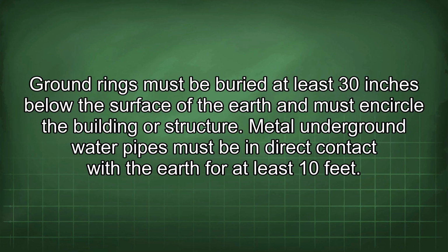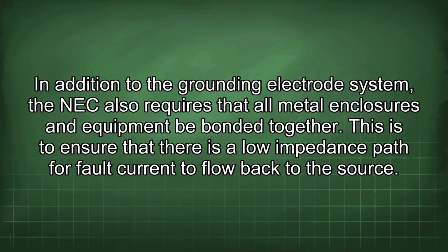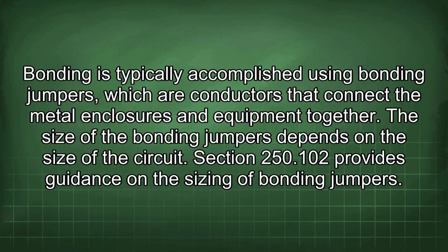Ground rings must be buried at least 30 inches below the surface of the earth and must encircle the building or structure. Metal underground water pipes must be in direct contact with the earth for at least 10 feet. In addition to the grounding electrode system, the NEC also requires that all metal enclosures and equipment be bonded together. This is to ensure that there is a low impedance path for fault current to flow back to the source. Bonding is typically accomplished using bonding jumpers, which are conductors that connect the metal enclosures and equipment together. The size of the bonding jumpers depends on the size of the circuit. Section 250.102 provides guidance on the sizing of bonding jumpers.